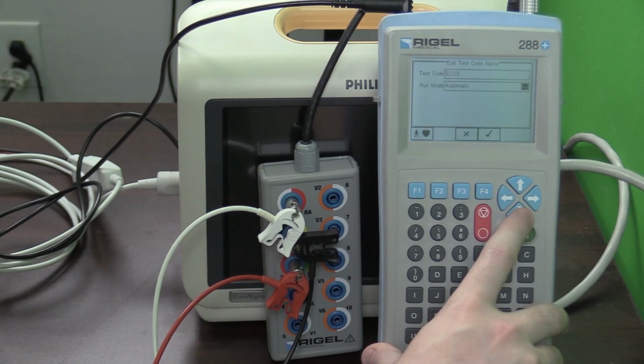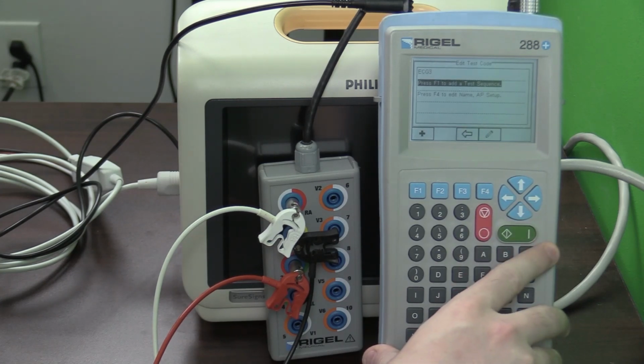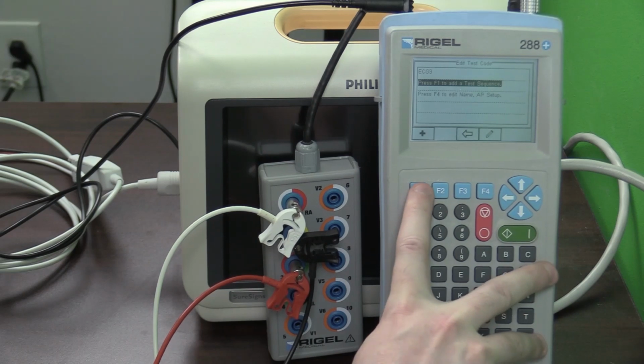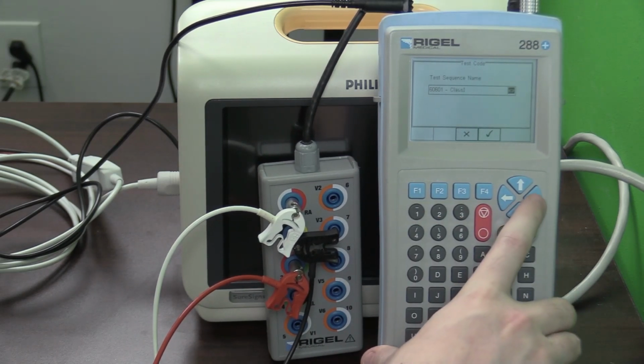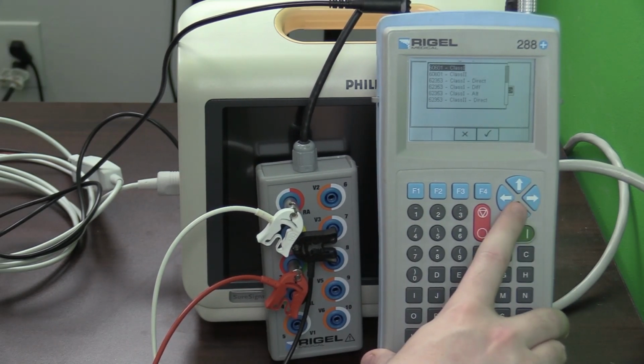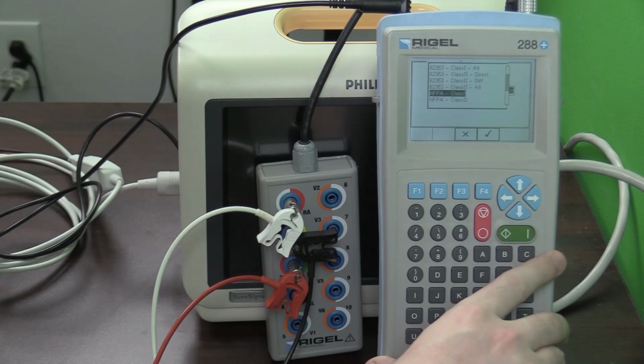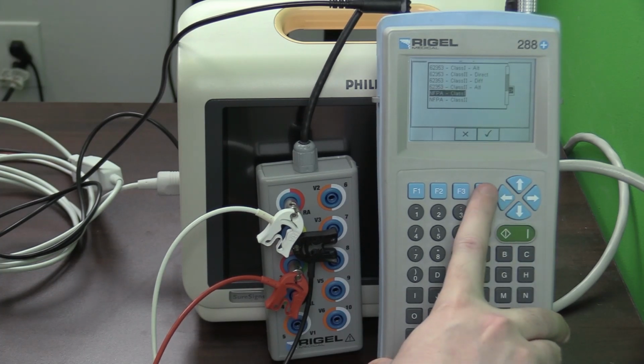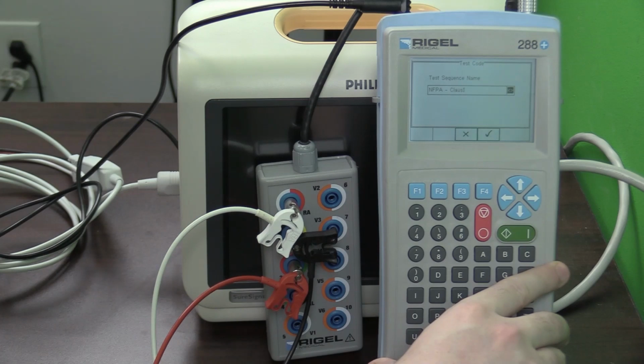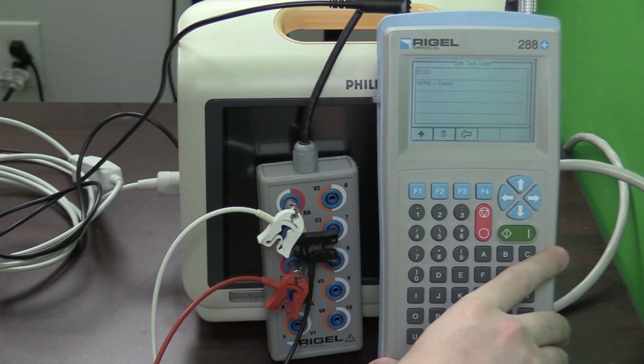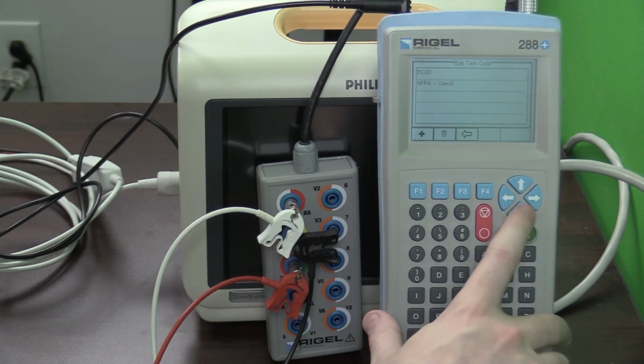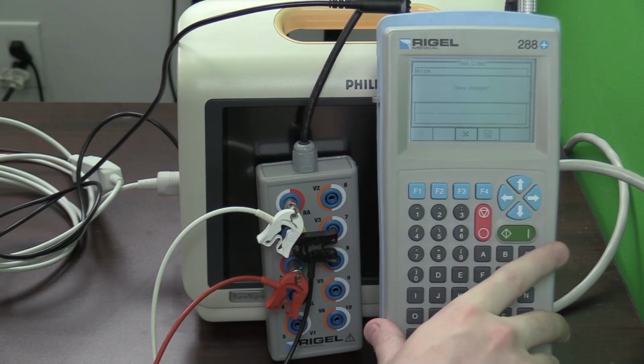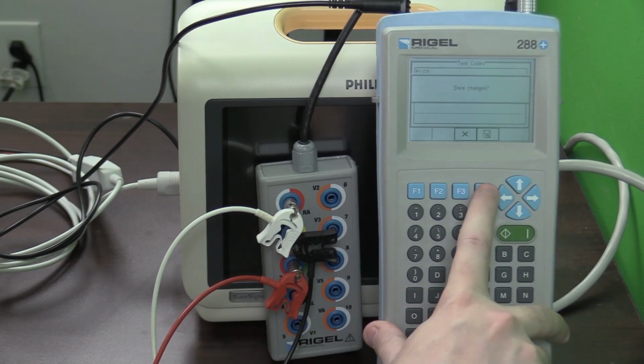Once you're back to this screen, select F4 again, and now you can get your actual test sequences. Select F1 to create a test sequence. This will be the standard that you're choosing to test. Right now we are doing NFPA, and my device is a class 1, so I'm going to choose NFPA class 1 and select F4 to choose that test sequence. F4 to save, and when you select F3, it's going to ask you if you want to save your changes. Select F4 to save those changes.